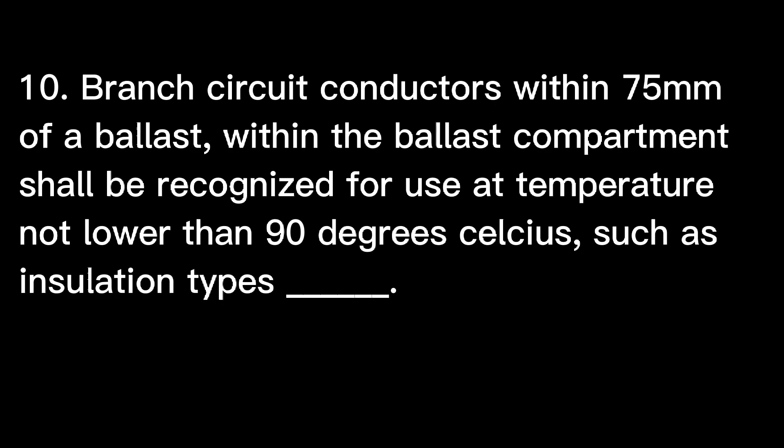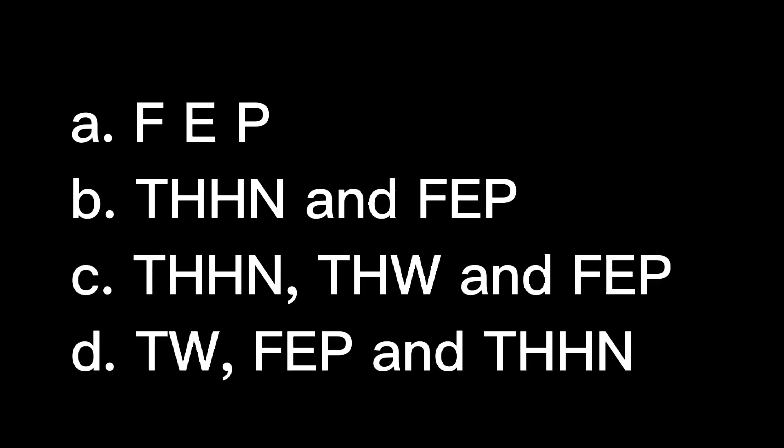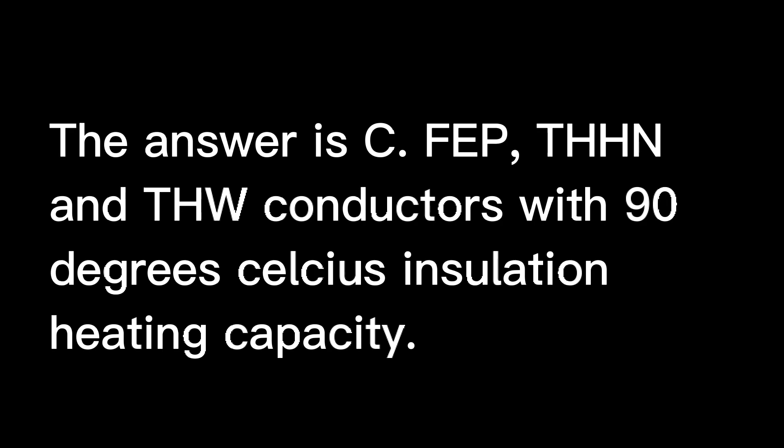Question 10: Branch circuit conductors within 75 mm of a ballast within the ballast compartment shall be recognized for use at temperature not lower than 90 degrees Celsius, such as insulation types: A. FEP, B. THHN and FEP, C. THHN, THW and FEP, D. TW, FEP and THHN. The answer is C. FEP, THHN, and THW conductors with 90 degrees Celsius insulation heating capacity.